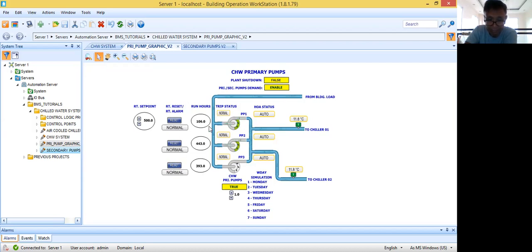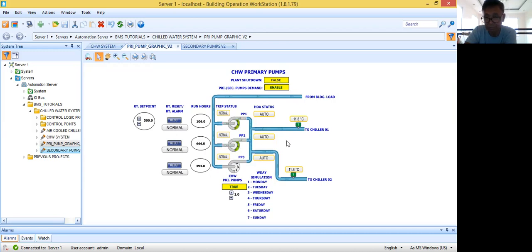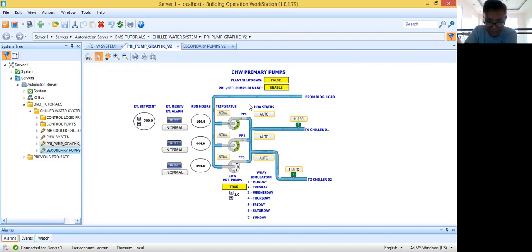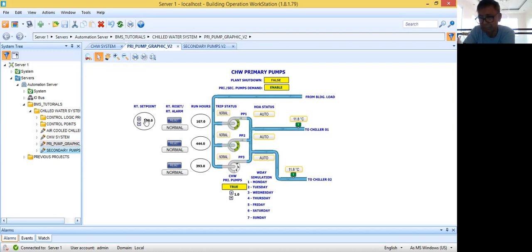If the pump runs 500 hours, there will be a runtime alarm — that will be the signal for the BMS operator to relay to the maintenance people that they need to do preventive maintenance. If you have BMS software that will automatically create a maintenance job order, that will be even better. I also have the trip status column — with a normal indication — and I have the hand-off-auto status, which is very important. So: hand-off-auto, trip, run hours, runtime reset, runtime alarm, and runtime setpoint are the most important points to show in your BMS graphic to help maintenance people.